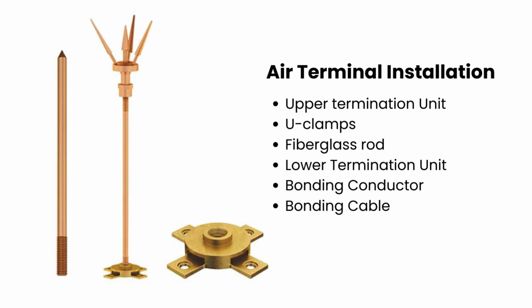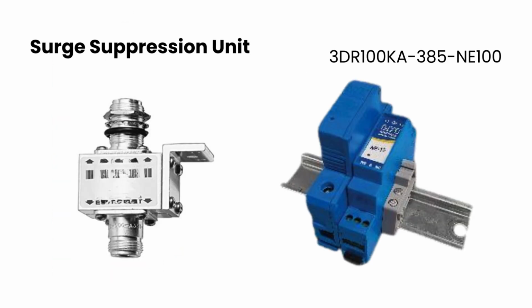The crucial components of this unit summarize into upper termination unit, U-clamps, fiberglass rod, lower termination unit, bonding conductor, bonding cable. The bonding or the shielding cable connects the air terminal to an earthing clamp that acts as ground screws. The surge suppression unit contains individual breakers and fuses, and the interconnection to a surge box. These contain single-phase and three-phase power supply protection kits of different ratings. A common example is that of the trademark 3DR100KA-385-NE100 surge protection setup.